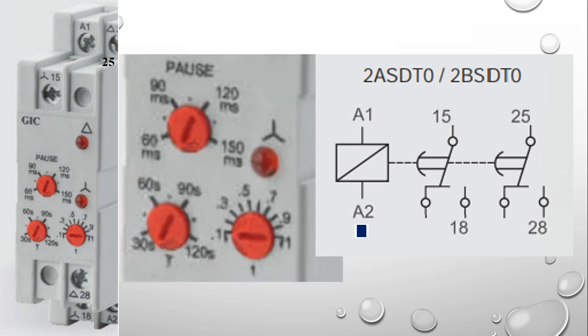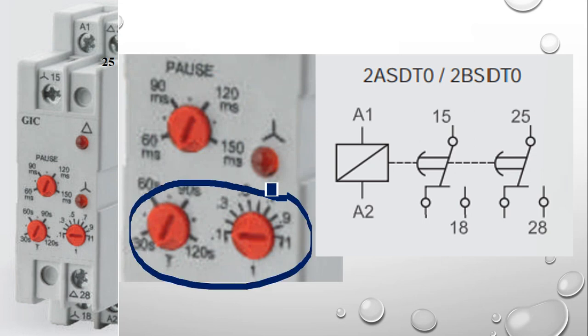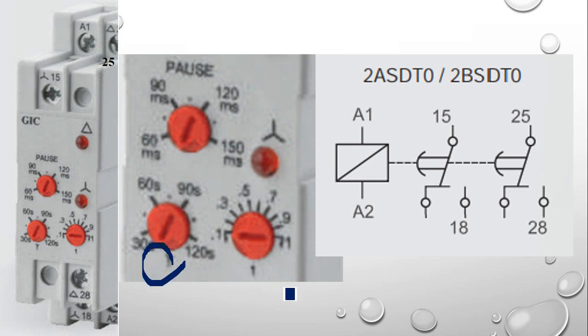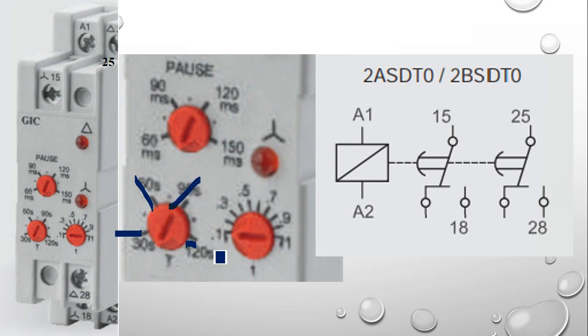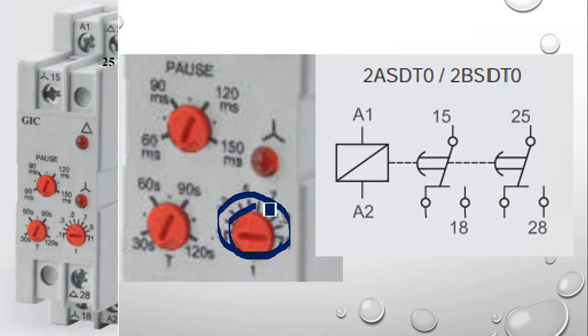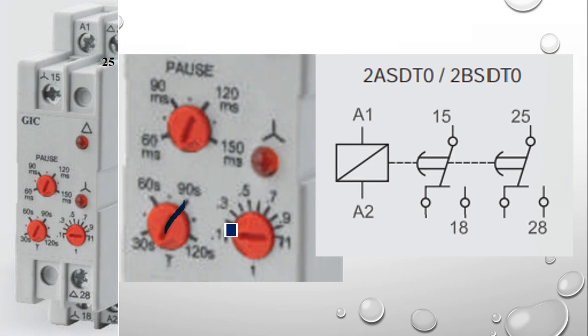To set the time, there are two setting positions adjusted by screwdriver. The main time setting 'T' has options of 30, 60, 90, and 120 seconds. A second setting 'small t' is a multiplier with values 0.1, 0.3, 0.5, 0.7, 0.9, and 1. The effective time equals T multiplied by t. For example, setting T to 90 seconds and t to 0.5 gives an effective time of 45 seconds.